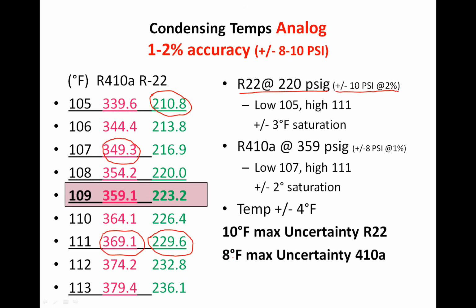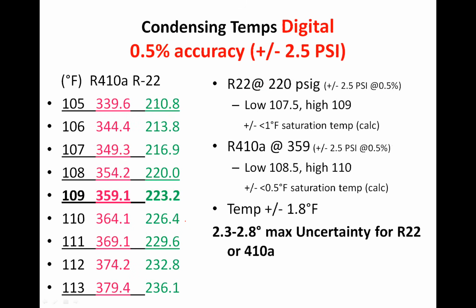We simply cannot meet the targets the manufacturers want with this technology. Now, if we shift and look at the same condensing temps with a digital gauge, with 0.5% accuracy, we're looking at plus or minus 2.5 psi. So again, we're going to start here with 220. At 220, plus or minus 2, the low goes to 107.5 and the high goes to 109. You can see we don't even change 1 degree in saturation temperature, because this is 216. So we don't even change by a degree in saturation temperature. And we've got a temperature uncertainty of plus or minus 1.8. So that takes our total uncertainty between 2.3 and 2.8 for R22 or 410A.